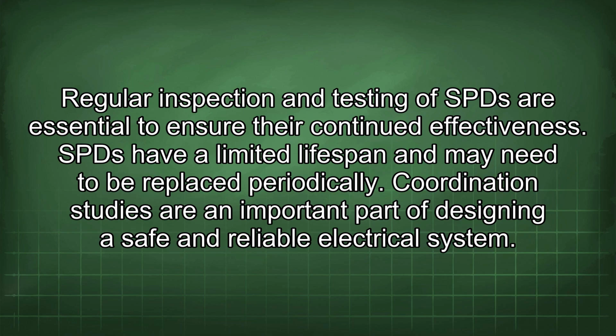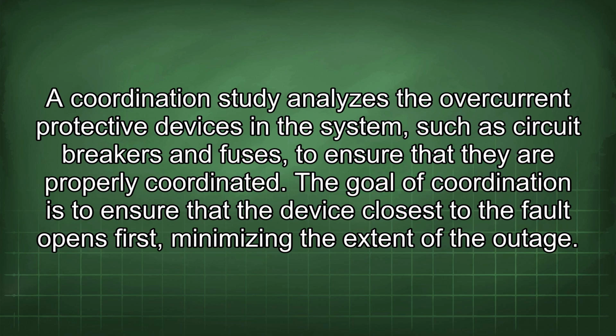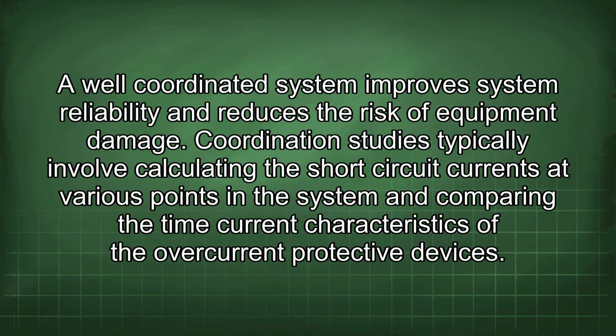Coordination studies are an important part of designing a safe and reliable electrical system. A coordination study analyzes the overcurrent protective devices in the system, such as circuit breakers and fuses, to ensure that they are properly coordinated. The goal of coordination is to ensure that the device closest to the fault opens first, minimizing the extent of the outage. A well-coordinated system improves system reliability and reduces the risk of equipment damage.